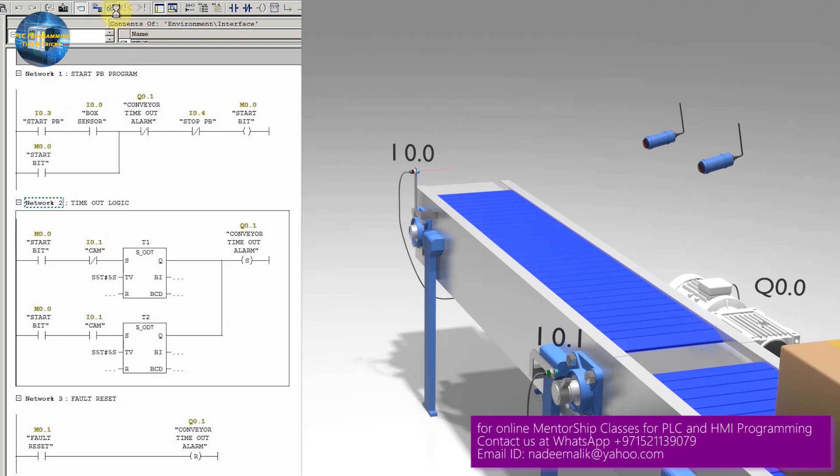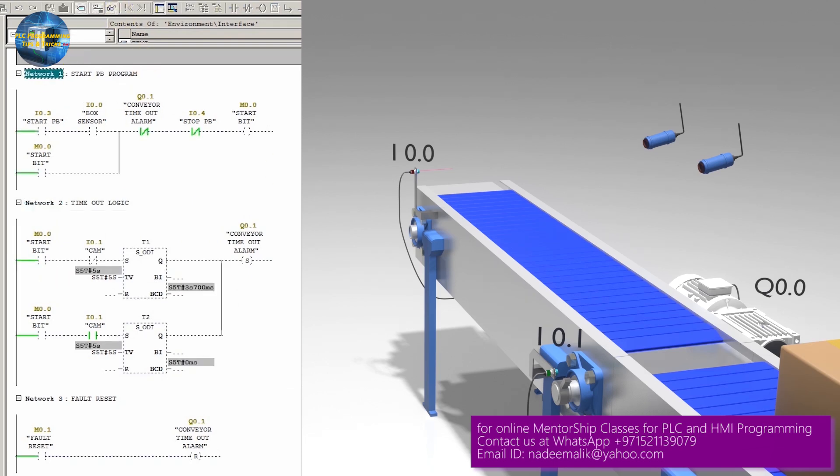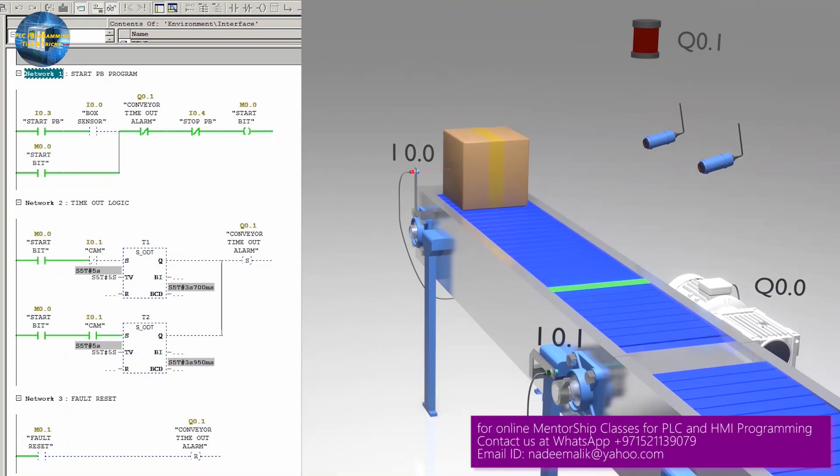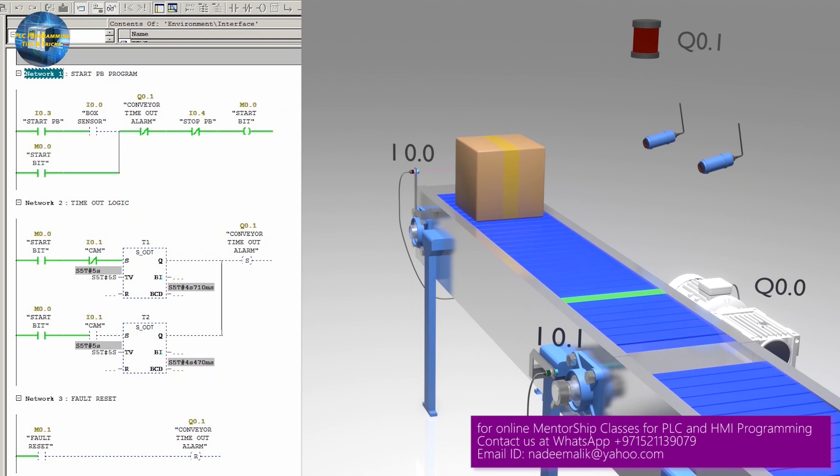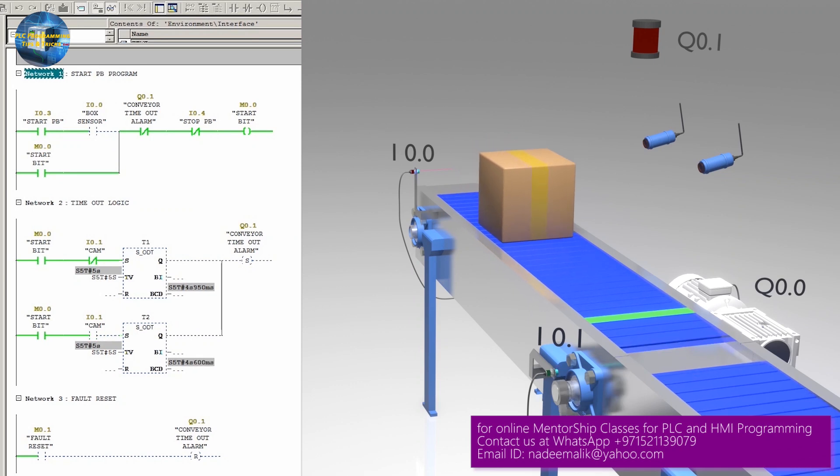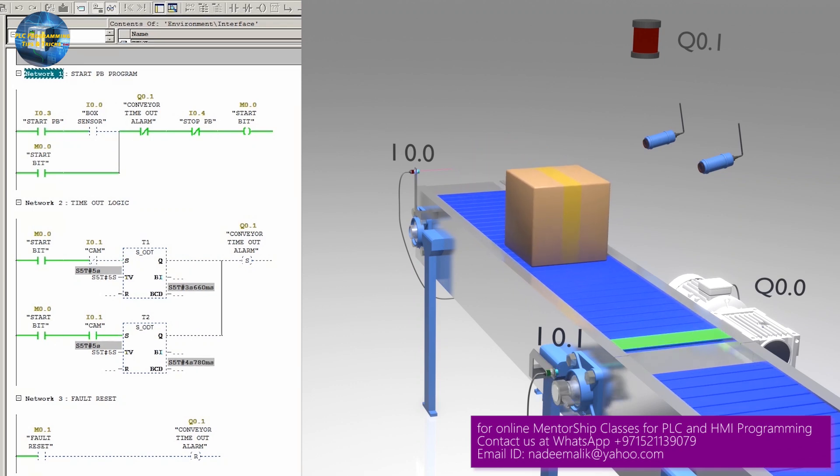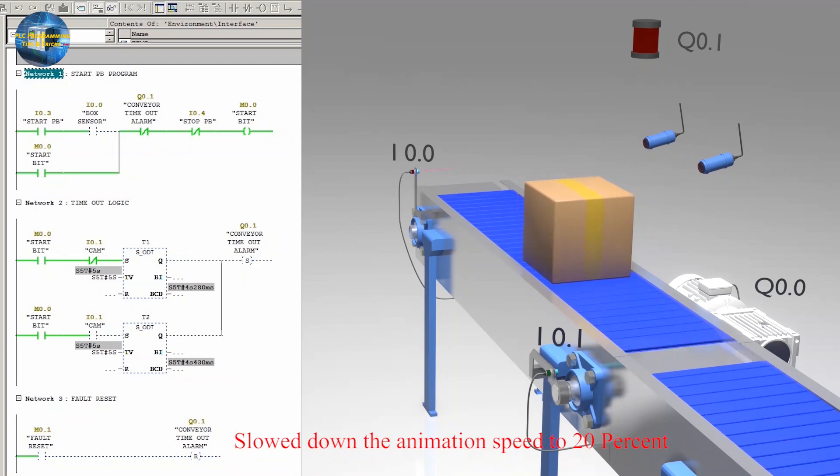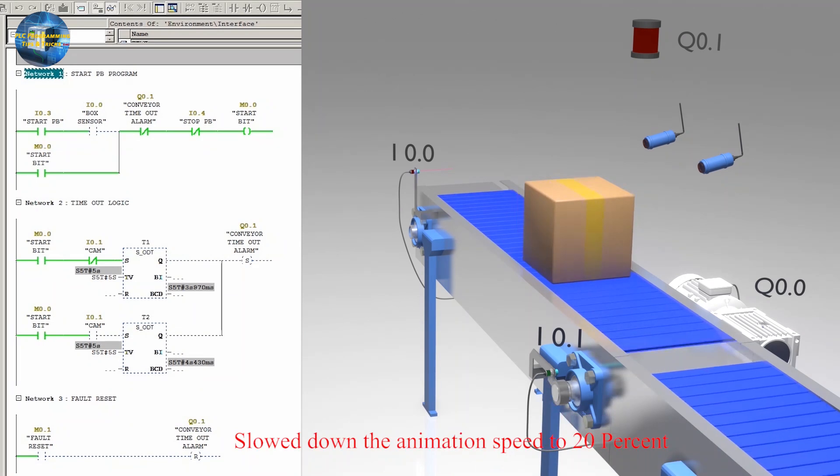Now we will start the process by pressing the push button I0.3. As the box comes in front of the sensor I0.0, the conveyor starts and box starts to move forward on the belt. Now as the conveyor belt malfunctions and stops, the cam is not in front of the sensor I0.1.